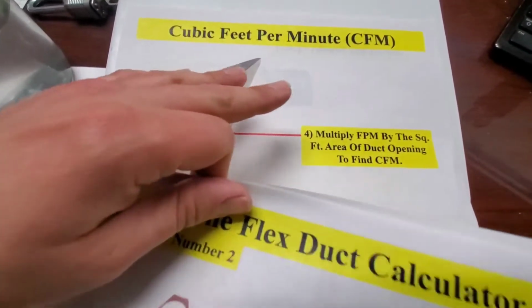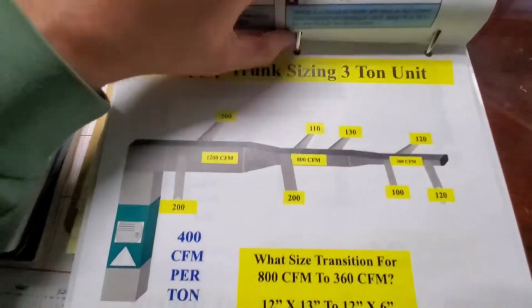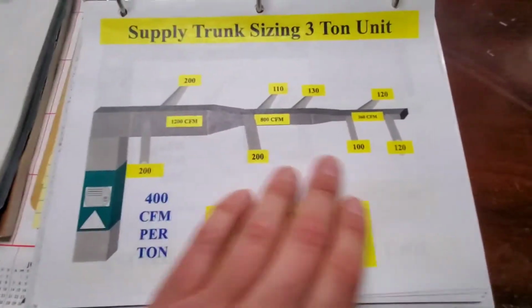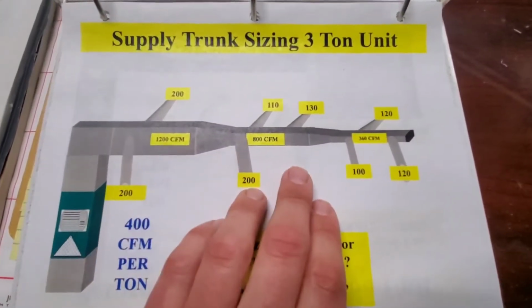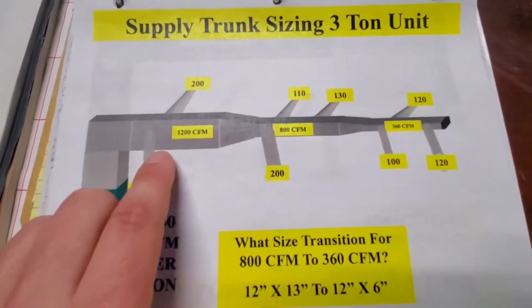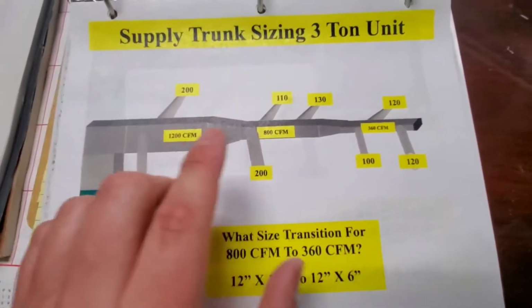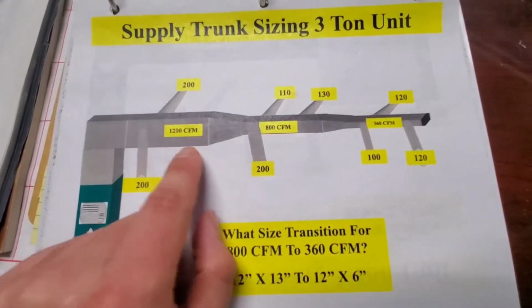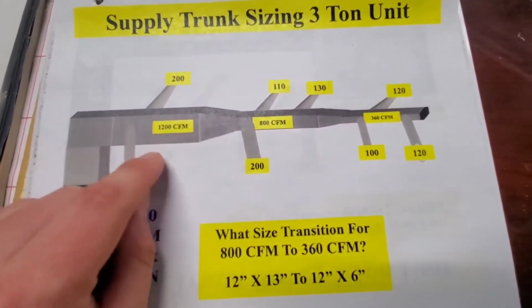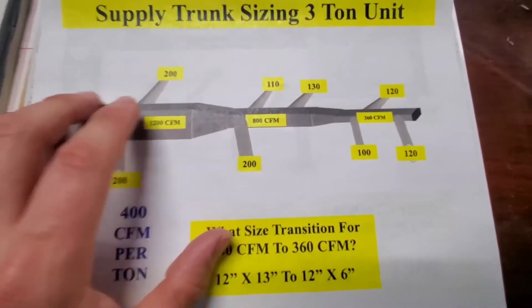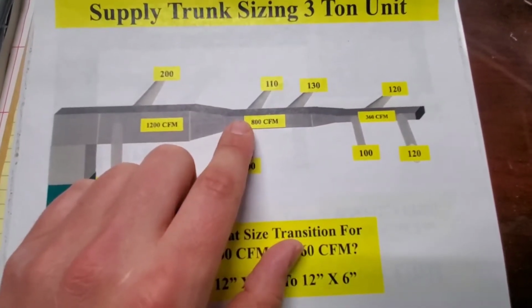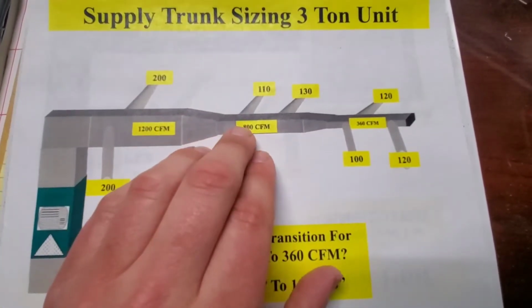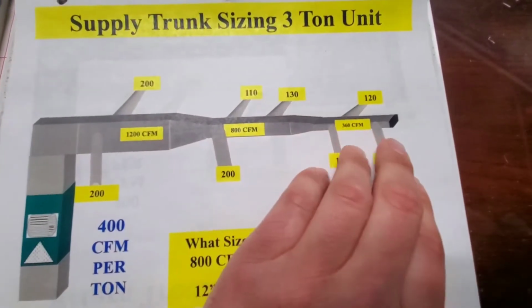Cubic feet per minute is what CFM stands for. And this is what a typical duct system looks like. This is a reduced plenum system. This is what we typically install. You can see there are different sizes of duct depending on how long your ductwork has to be, and how many sizes you need. And what you do is every 30% you reduce the size. That way you're equaling out the CFM you need for the lines that you have left, okay?